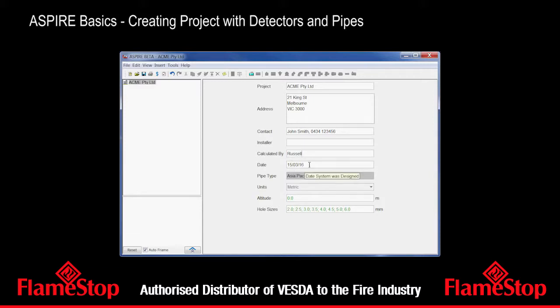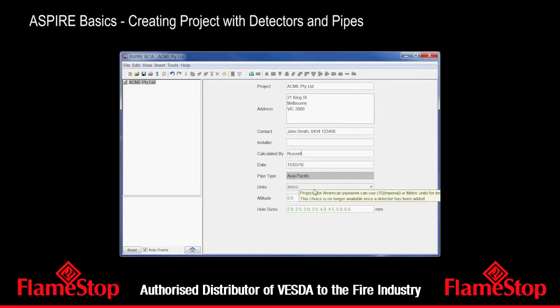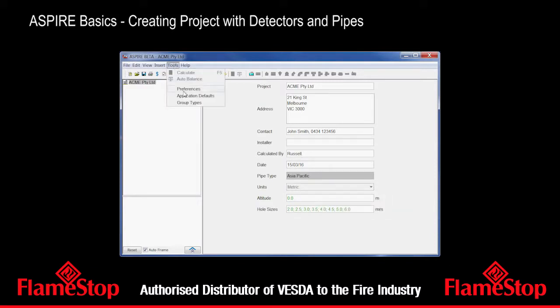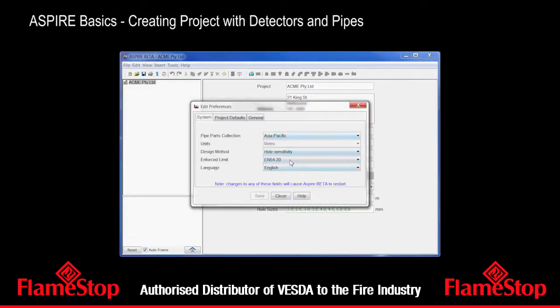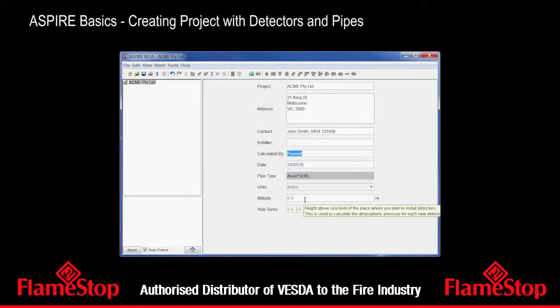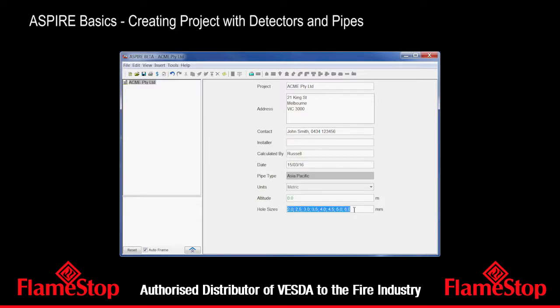The date defaults to today's date. We can change it if we want to, but usually don't need to. Now these two settings here are important — they dictate the type of bends and other components we use. They're set up under preferences and really need to be set before we even create the project. The altitude is only important where you've got considerable altitude, such as La Paz at 4,000 metres — you definitely want to enter that. For cities at or near sea level, you don't need to bother. The set of hole sizes basically lists the type of drill bits the installer is going to use.